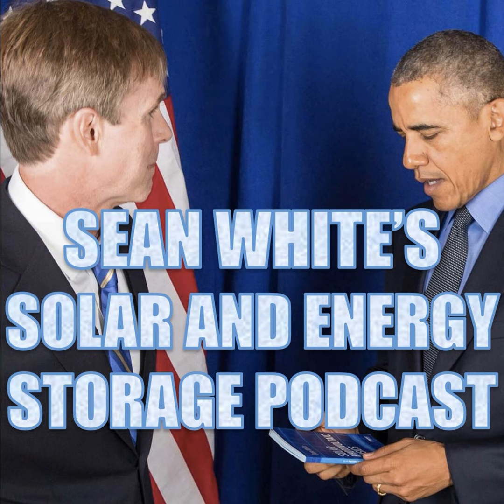Sometimes what we're seeing in this modern age is the battery inverter and the energy storage system all in one device. That's the way that Tesla Powerwall does it these days. So you would have an energy storage system and an inverter charger that's all in one, and that would be an AC coupled system. If you're working with SolarEdge and doing energy storage, they have a DC coupled solution. So that means that you have the PV and the energy storage coming together on the DC side of an inverter. So they're coupled together on the DC side.